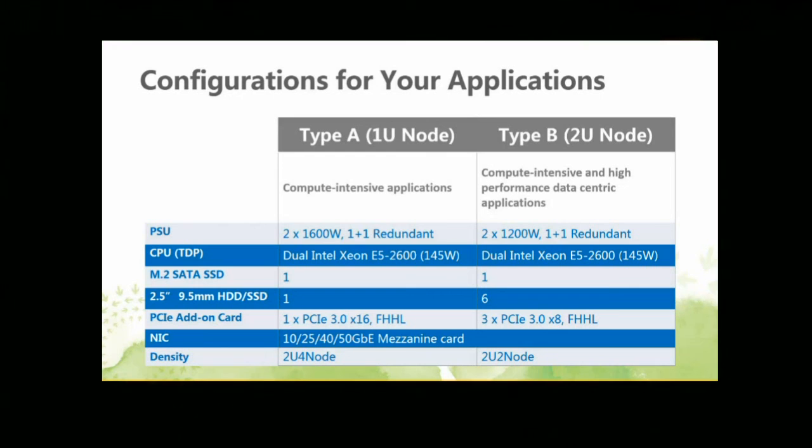Yeah, there are different architectures. So it really depends on what power I can deliver to the rack, the EIA rack, because there's no power in the rack. And for OCP, it's the power shelf itself attached to the rack. What we can compare right now is the physical space. If you take a 42U EIA rack, maybe you need a switch, and then you have 40U, and 40U, then you will have 80 servers. That's the limitation from the real estate, but it also depends on the cooling and the power that you can support for all the 80 servers.